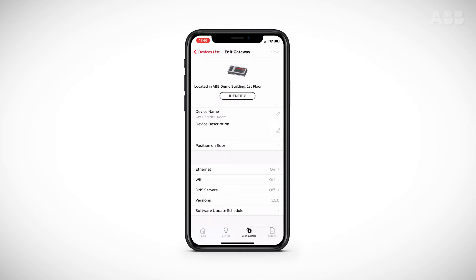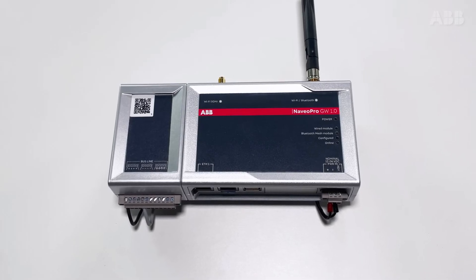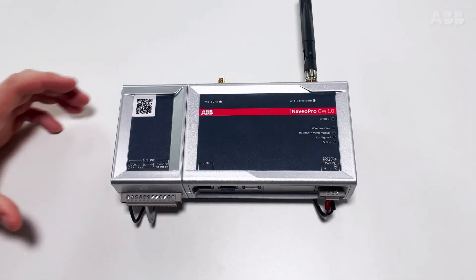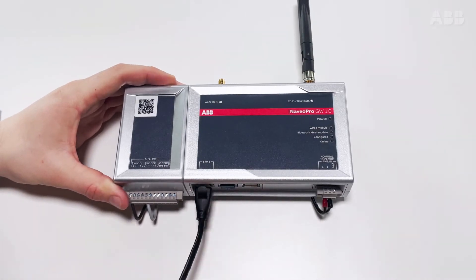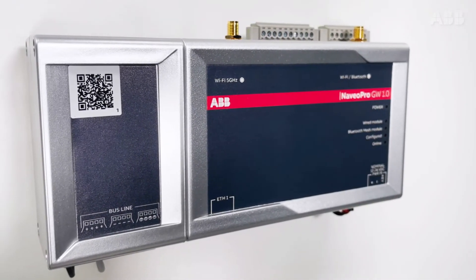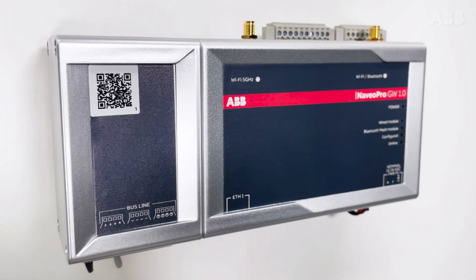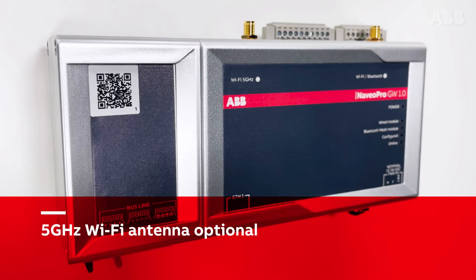Depending on the type of internet connection available in your building, select Ethernet or Wi-Fi. If the installation site has a wired operating Ethernet network, connect the cable to the gateway's Ethernet port. Otherwise, a Wi-Fi internet connection can be used. The NaveoPro gateway is compatible with 2.4 GHz and 5 GHz Wi-Fi. For the use of 5 GHz Wi-Fi, the specific antenna is available as an option.